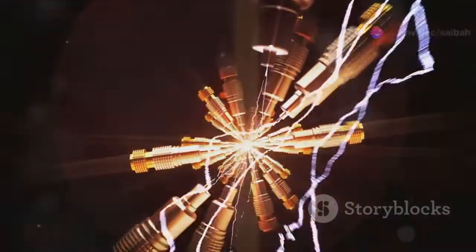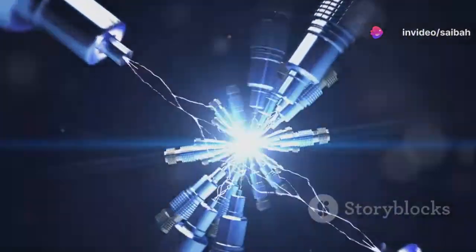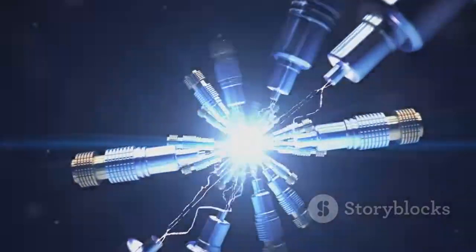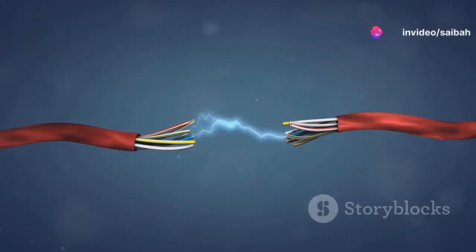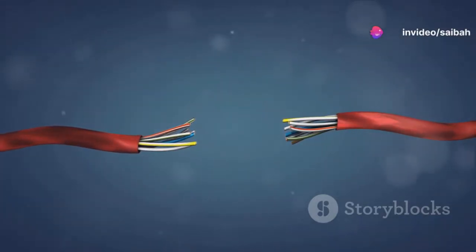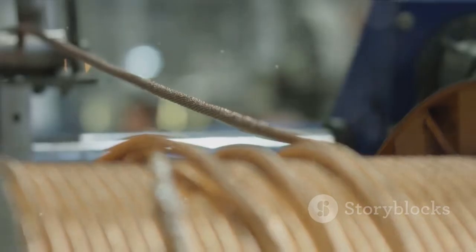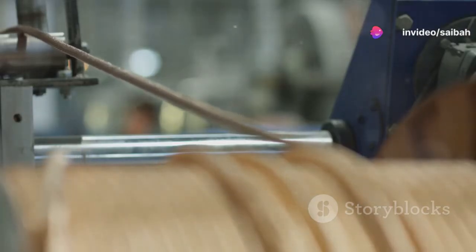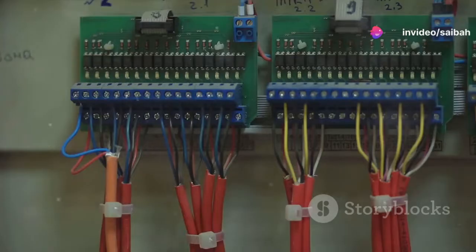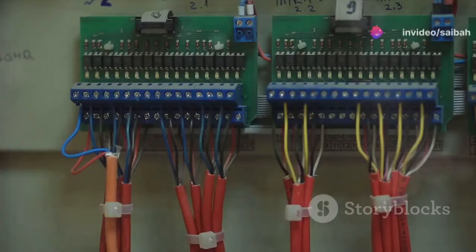Now, you might think that all cable shields are created equal. However, electronic and power cable shields, despite their similar appearance, perform vastly different functions. Electronic cable shields are designed to minimize the effects of external electromagnetic signals on the conductors within the cable. At the same time, they work diligently to reduce the radiated signal from the cable to an acceptable level. On the other hand, power cable shields play a critical role in protecting us from shock hazards and increasing cable reliability. They prevent partial discharges, also known as corona, within the cables. The National Electrical Code even requires most cables rated 2400 volts or greater to be shielded.